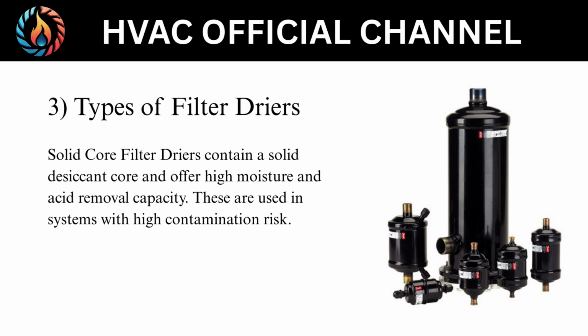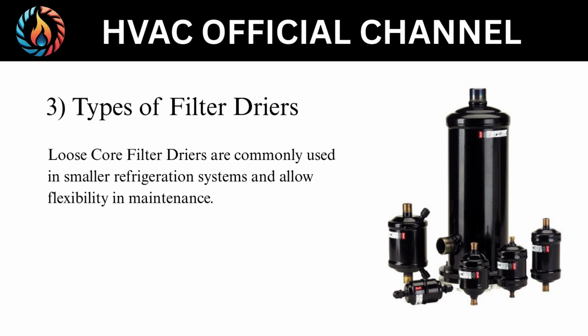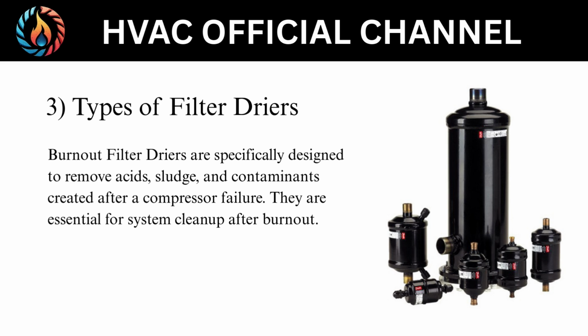Solid core filter dryers contain a solid desiccant core and offer high moisture and acid removal capacity. These are used in systems with high contamination risk. Loose core filter dryers are commonly used in smaller refrigeration systems and allow flexibility in maintenance. Burnout filter dryers are specifically designed to remove acids, sludge, and contaminants created after a compressor failure. They are essential for system cleanup after burnout.